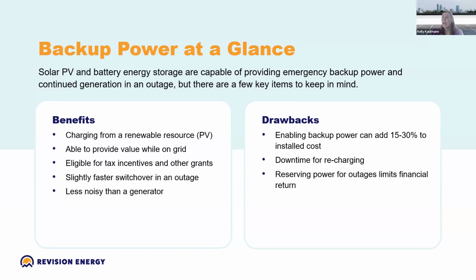It does have a slightly faster switchover rate in an outage compared to a diesel or propane generator, because it doesn't have ramp time the same way a generator might. This matters if you're looking to pair it with another generating resource like a diesel or propane generator. Usually what we've seen customers do is put their PV and battery system as the first line of defense in an outage, for that faster switchover and because those systems are usually already on. In that case, power from the battery is used until it's depleted.